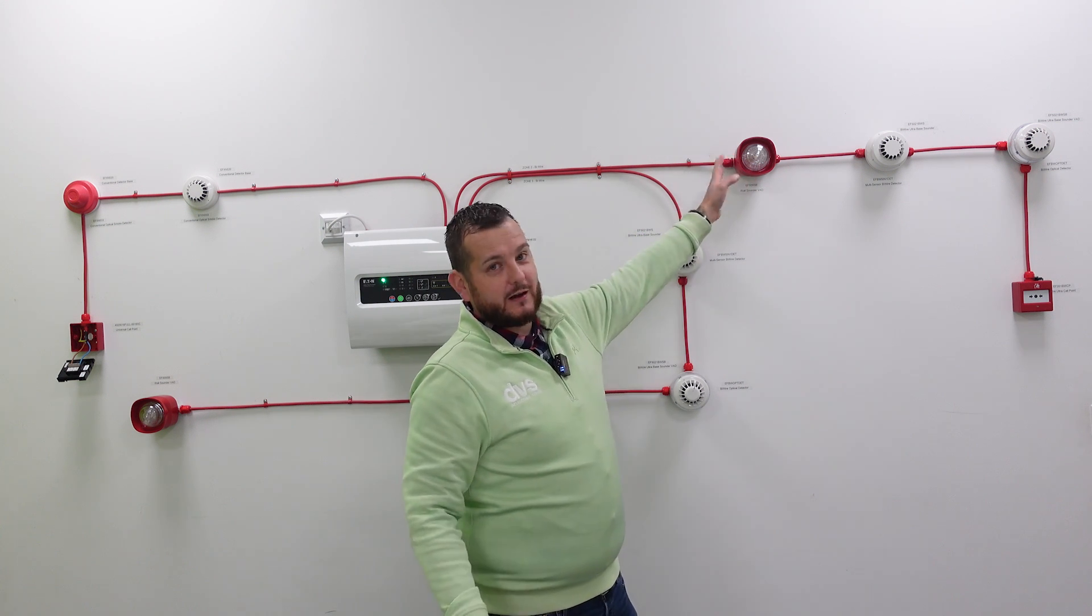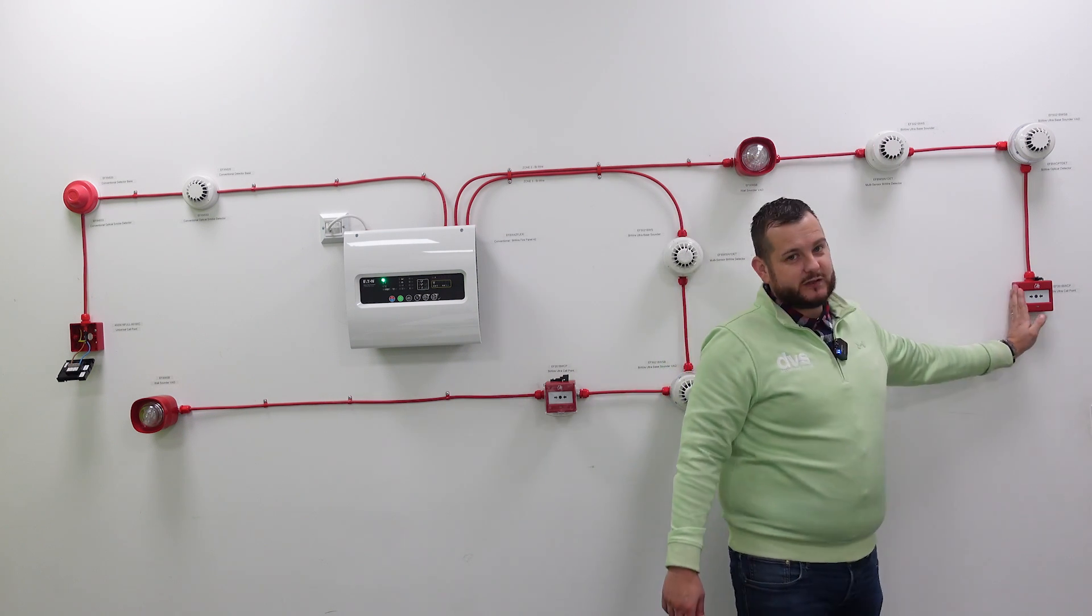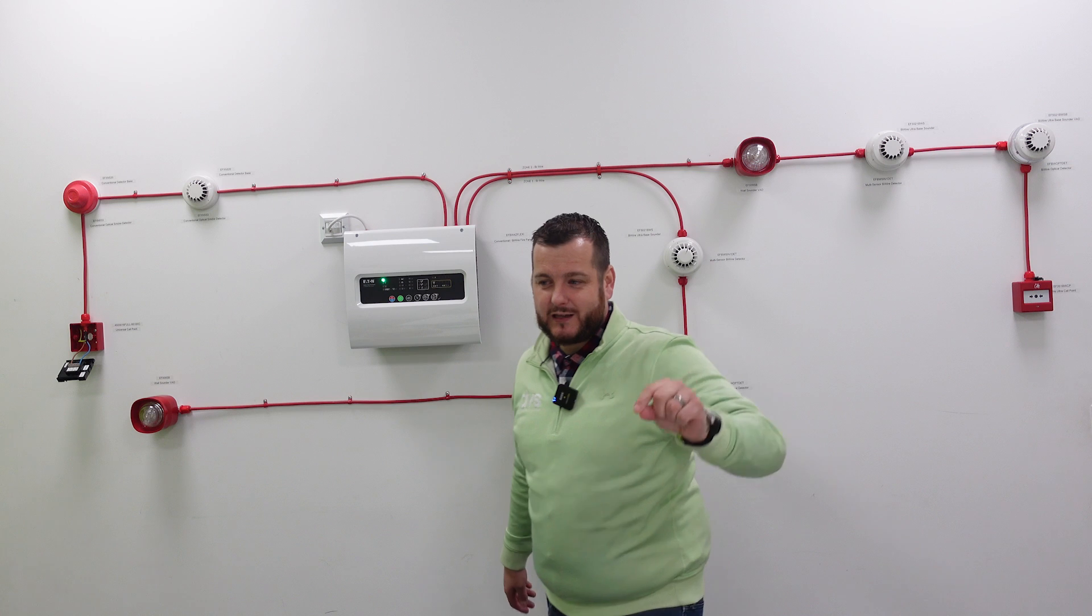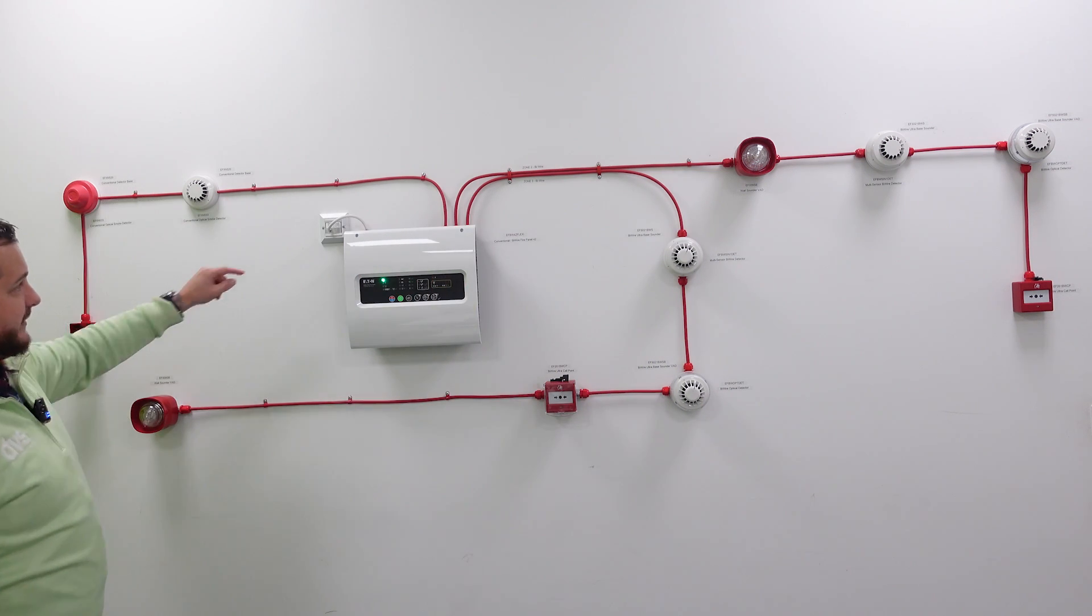Effectively using a single two core cable, like I've got in front of me, 1.5 millimeter two core enhanced cable from our partner, we're able to run out to the VAD, detector, to the VAD alarm sounder, so visual and audio device, then we've got our detection and our MCPs, our manual call points, on the same cable.